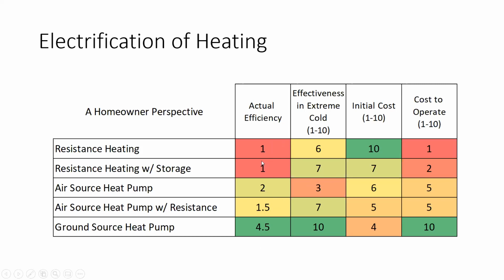Oh, I'm real sorry. COP is how much heat you get out for the electricity you put in. If you put in a kilowatt of electricity and you get a kilowatt of heat, that's a COP of 1. If you put in a kilowatt of electricity and get 4.5 kilowatts of heat, thermal energy, that's a COP, a coefficient of performance of 4.5. And that's what you'd see typically with a ground source heat pump. Sorry to take you down that road without any definitions.